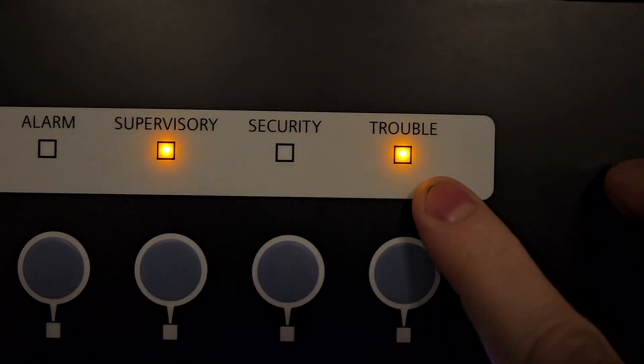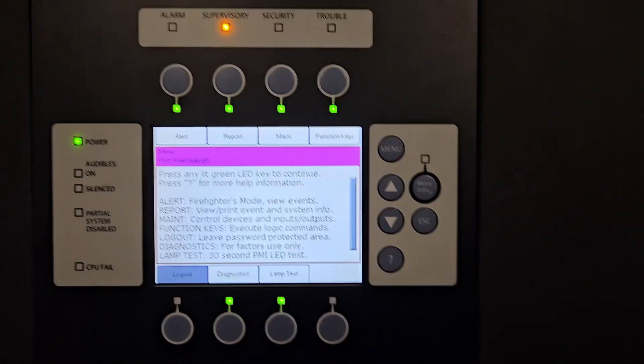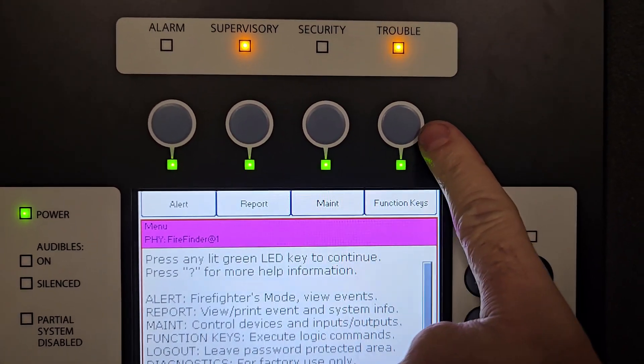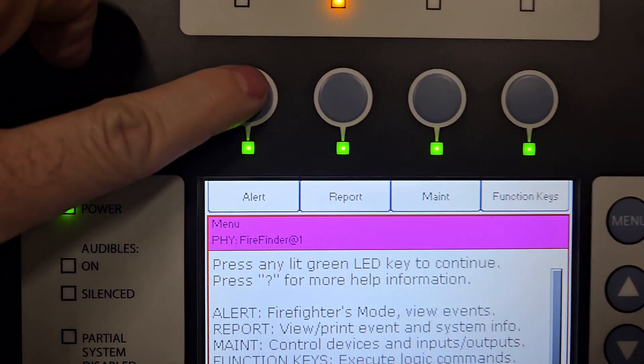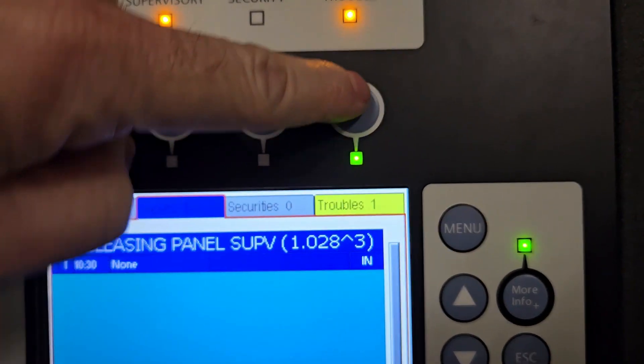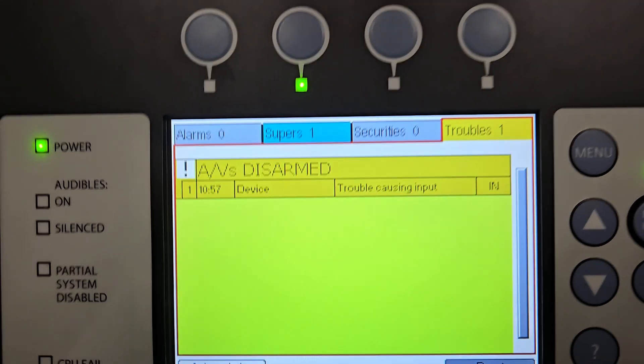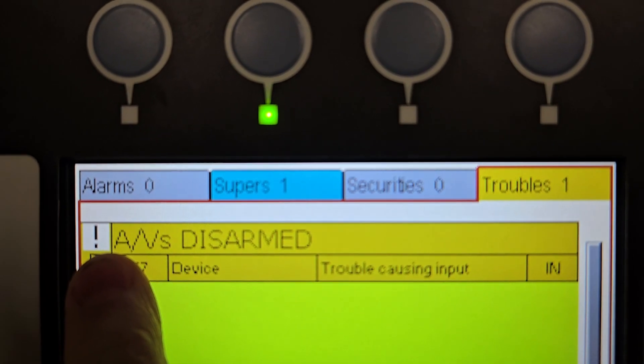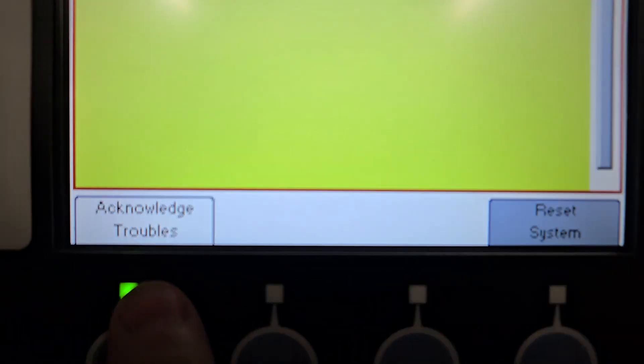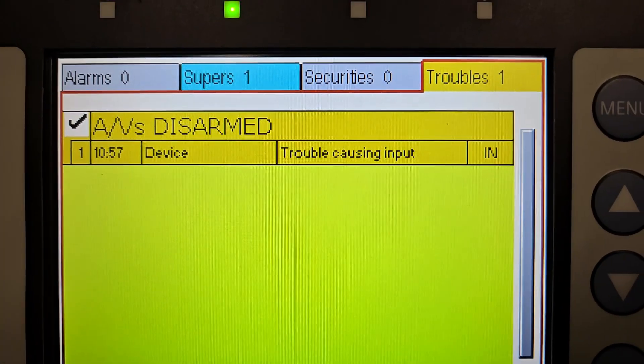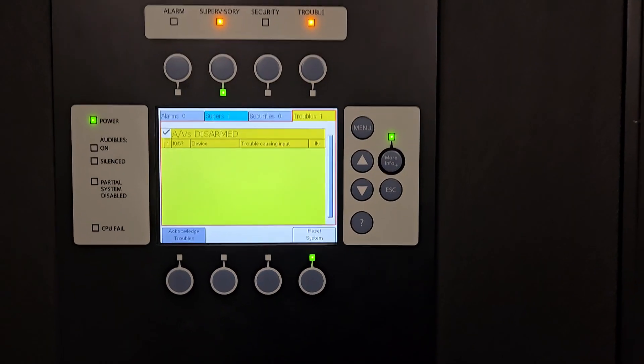I have my trouble coming in here. I'm going to hit the menu button to go out to the menu screen. On the left, I'm going to go to alert. You see I have supervisories and troubles, and I have the audio-video disabled flashing with an exclamation mark. I'm going to hit the acknowledge button in the lower left to silence the panel. Now the panel is silenced and my AV is disarmed, so I can do testing without the horn strobes going off.